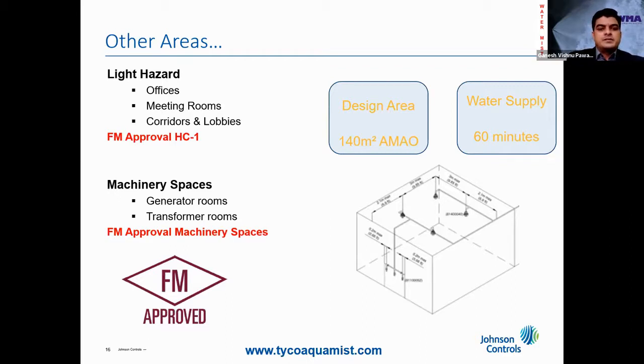Whereas machinery space areas such as the generator rooms and the indoor transformers can be protected with a total flooding application. Here you can see on the right hand side image, this is the room which has open nozzles in it, and it protects everything inside the enclosed room. Hence it is called a total flooding application. And this is a deluge configuration. Again, these systems are in line with the FM approval.